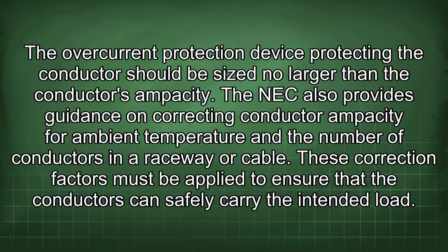The NEC also provides guidance on correcting conductor ampacity for ambient temperature and the number of conductors in a raceway or cable. These correction factors must be applied to ensure that the conductors can safely carry the intended load.